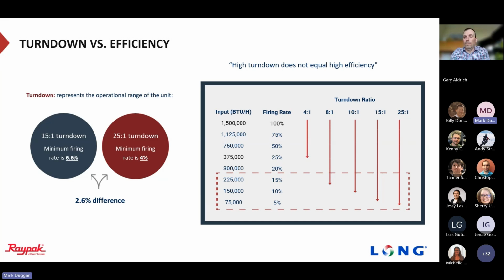Where you see those benefits is more on the residential side, where you're only heating up maybe one zone at a time. On a commercial application, you may still get those low firing rates in that shoulder season where you're only needing to run it in the morning or in the evening. But even in that application, typically that boiler is going to be running at 10% or higher, between 10 and 20%. We really don't see those boilers run at 6% or 4% very often. So high turn down does not always equal high efficiency.